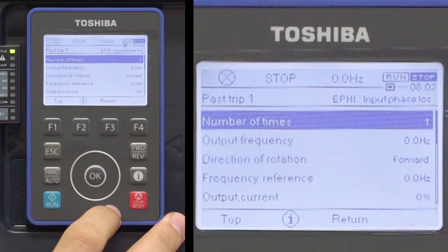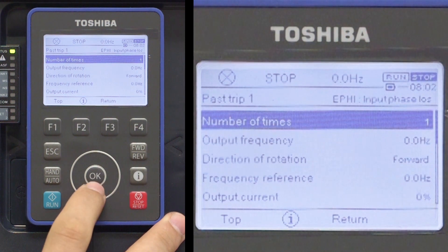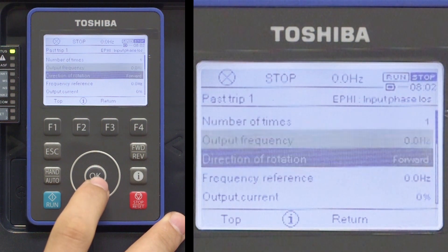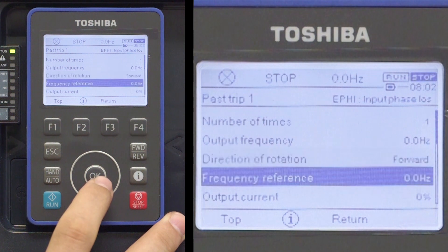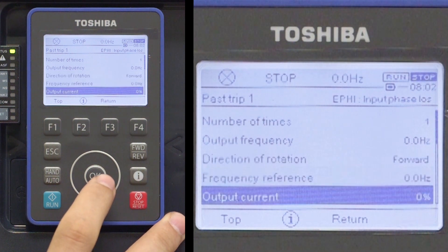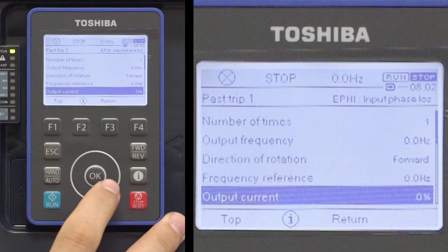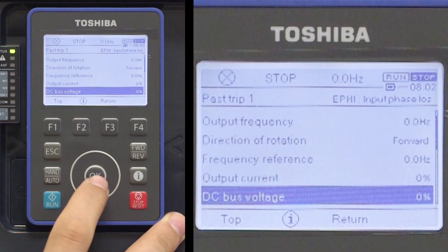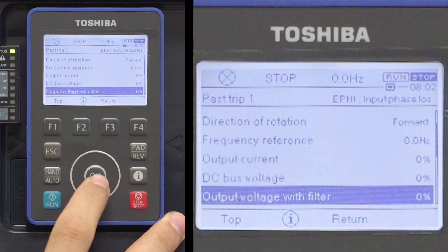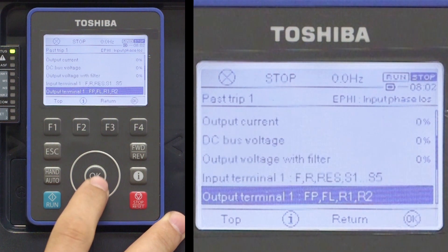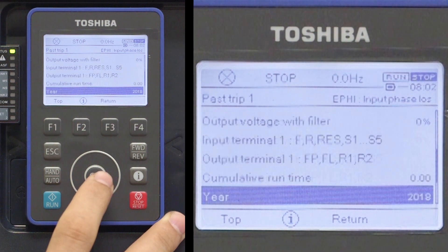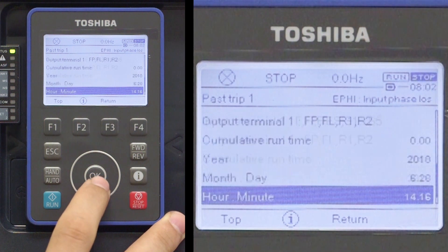This information includes number of occurrences, output frequency, direction, commanded frequency, output current, DC bus voltage, output voltage, discrete I/O status, cumulative runtime, and the time and date the trip occurred, and the internal temperature.